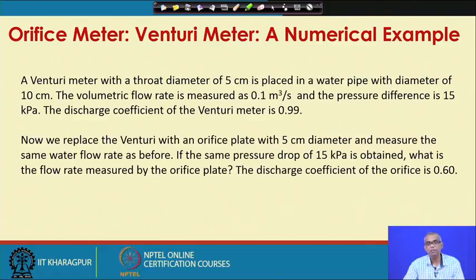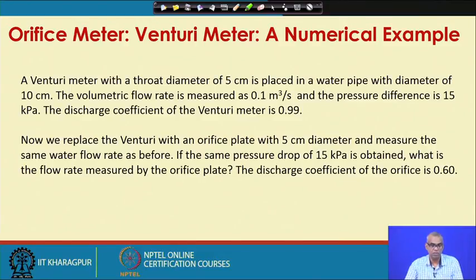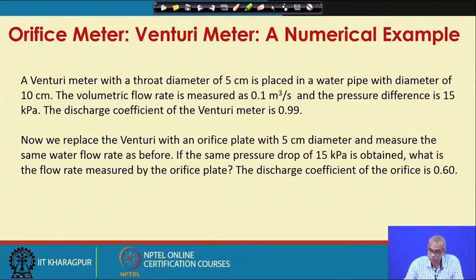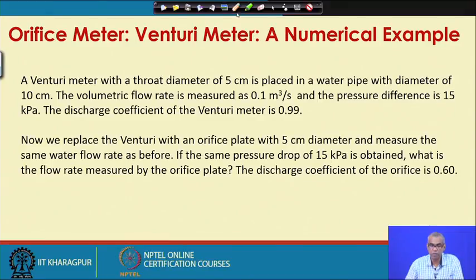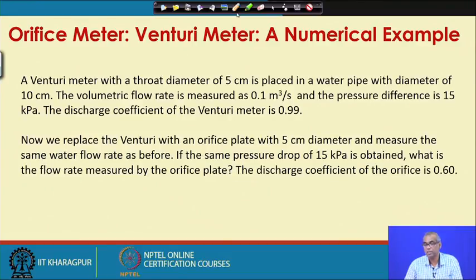Let us take a numerical example involving measurement of flow with orifice meter and venturi meter. A venturi meter with a throat diameter of 5 cm is placed in a water pipe with diameter 10 cm. The volumetric flow rate is measured as 0.1 m³/s and the pressure difference is 15 kPa. The discharge coefficient of the venturi meter is 0.99. We then replace the venturi with an orifice plate with 5 cm diameter and measure the same water flow rate. If the same pressure drop of 15 kPa is obtained, what is the flow rate measured by the orifice plate? The discharge coefficient of the orifice plate is given as 0.60.